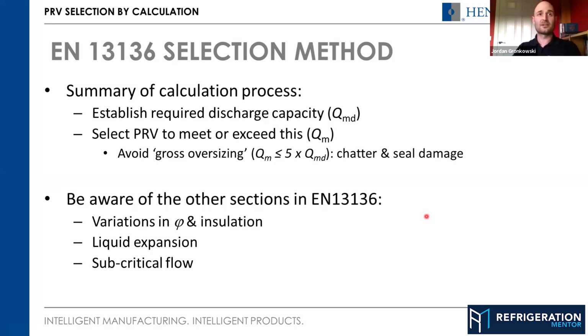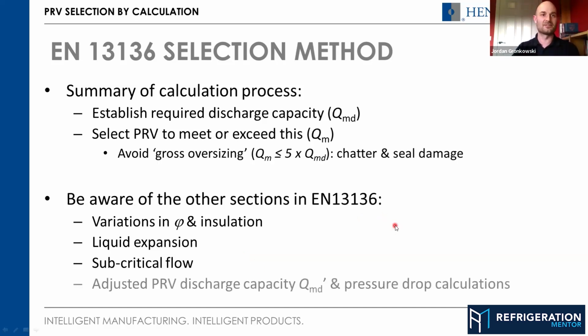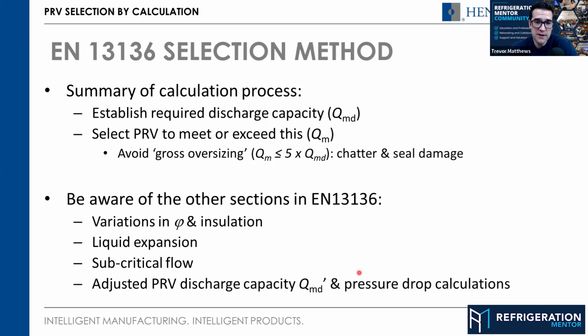Again, subcritical flow, as I spoke about earlier: most valves tend to be critical flow through the valve itself, so that term doesn't matter. But if you have a different valve, then the manufacturer will probably advise that you use a different term. And we'll talk in more detail later about the adjusted PRV discharge capacity, QMD dash, and the pressure drop calculations, which are a whole other branch of calculations that I won't get into in too much detail here. So before we move on, these are different standards within the code. Okay.